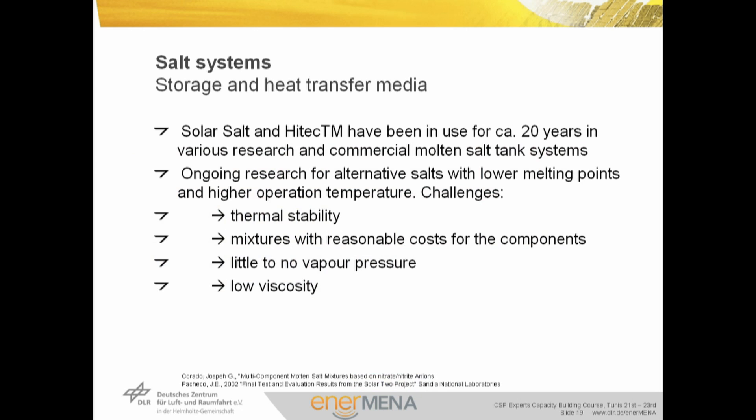The cost and properties of the molten salt determine the characteristics of a two-tank molten salt storage system. Significant improvements are only possible by applying improved salt systems. Current research focuses on identifying cost-effective alternative salt systems. A low freezing temperature is important, but other aspects such as thermal stability over a wide temperature range, low vapor pressure, and low viscosity to limit pumping power must also be considered.